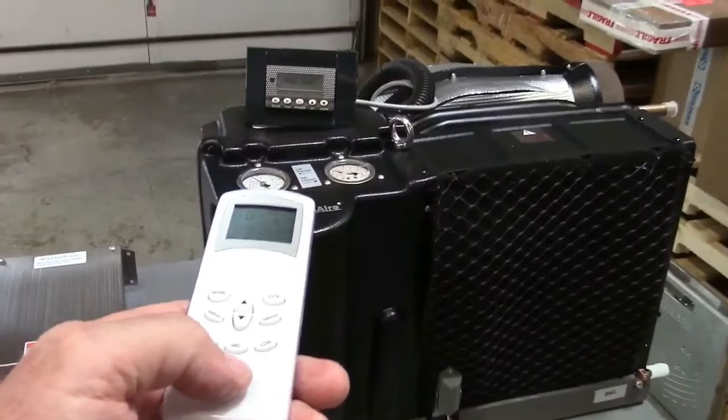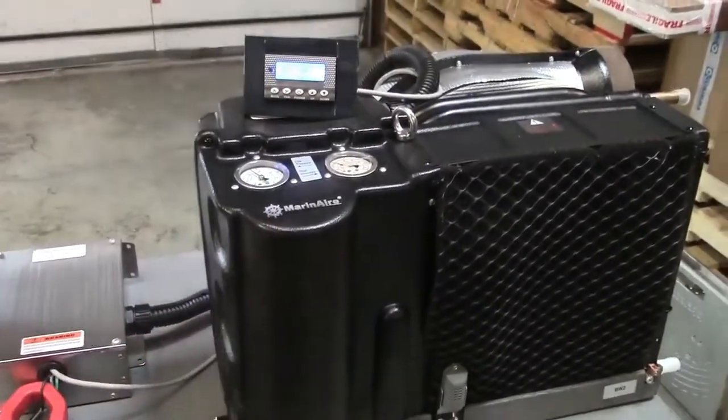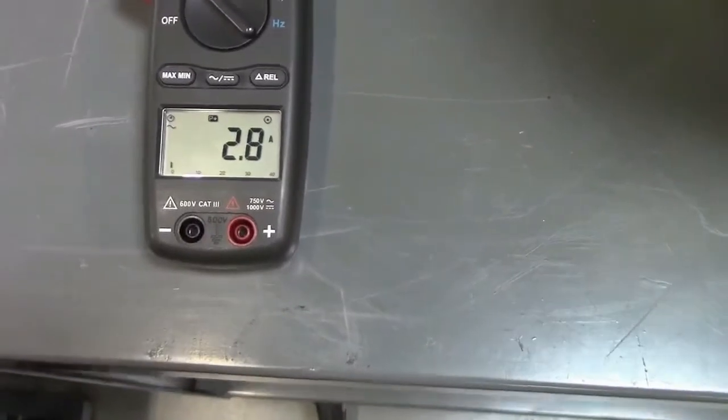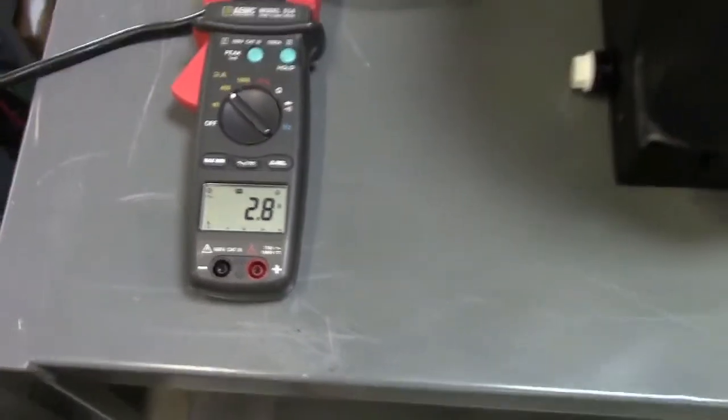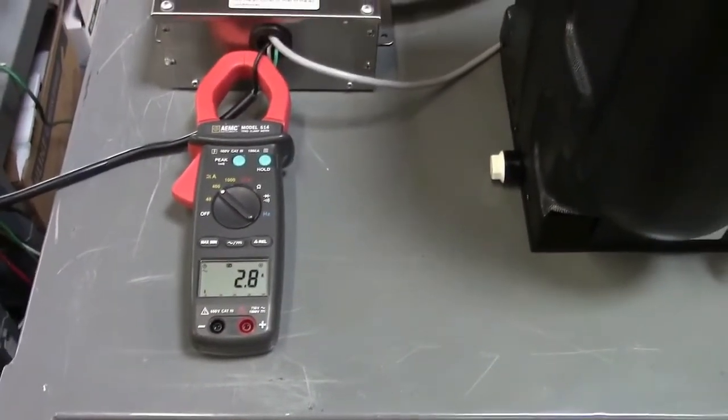So we go ahead and start up the unit. There's our display and there's our remote control. The fan starts up and immediately we've got a peak of 2.8 amps when the fan picked up.